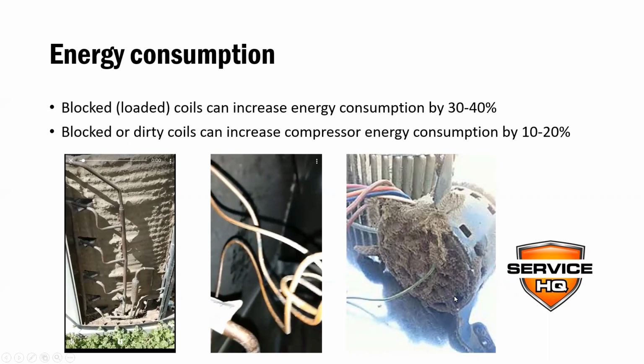Also, if you don't change the filter regularly, which we'll talk about in step one of doing the maintenance, this was an actual blower motor assembly that we pulled out. So here's the blower wheel in a furnace. Basically, this is what moves the air through your home, and then you can see just how caked with junk that gets from not being filtered properly. But this type of dirt can increase the compressor energy consumption, which makes it work harder. The harder it works, the more energy it consumes by 10 to 20%.